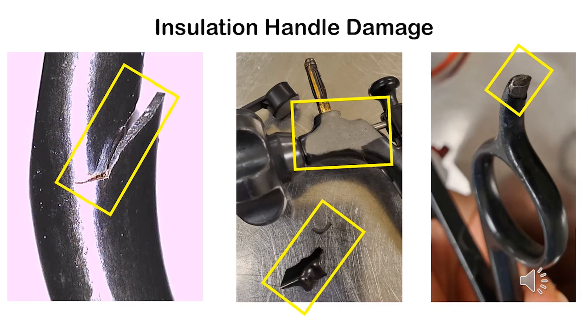The insulation handle, if you do have this, because they do come metal as well as plastic, but in insulated handles, you can see in the picture on the left, this is a complete split. The picture in the middle there, the insulation actually came off in my hand. The picture on the right, you can see that it's exposed metal here. This would not only catch the drape on fire and possibly burn the patient, this can actually burn right through the surgeon's glove.